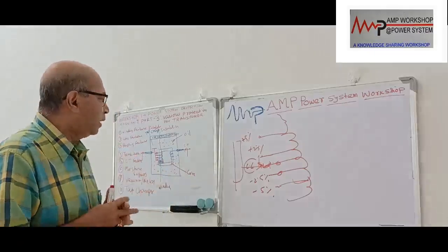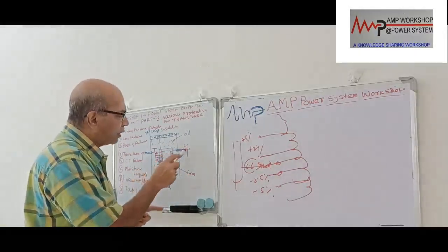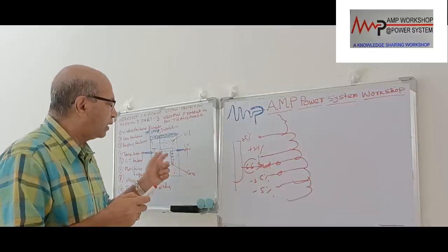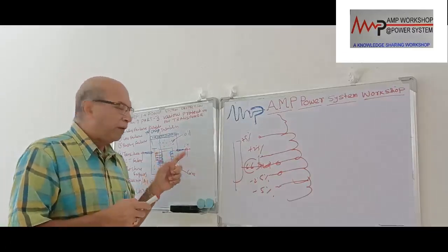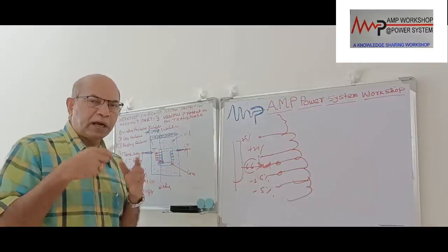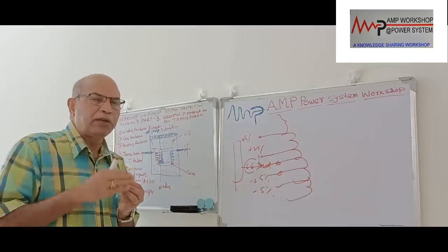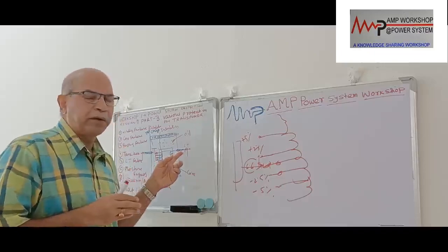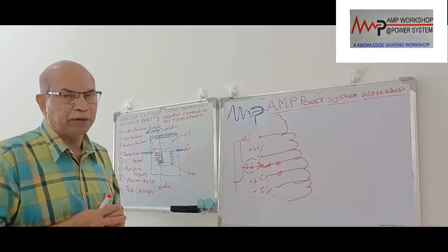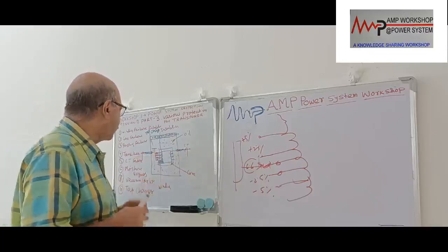This is another point. Then the bushing, which is connected to the transformer for inside to outside connection. This bushing can fail if it is in a very dirty or polluted area, where the 3-phase distance may be reduced. In that case, at the end terminal of the bushing, there would be a chance of flashover. So this bushing can also fail.